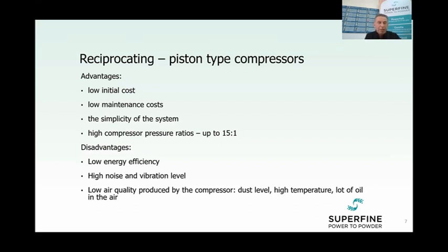But this type of compressor has some disadvantages. First of them is low energy efficiency, high noise and vibration level, and low air quality produced by the compressor in terms of dust level, high temperature, and a lot of oil in the air.